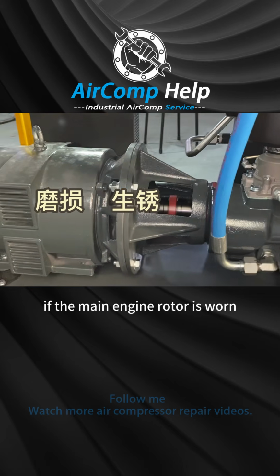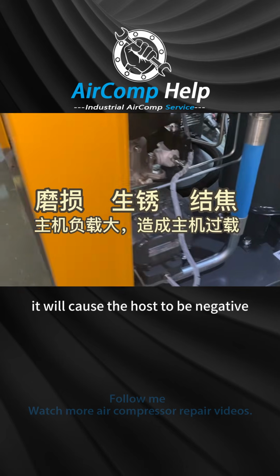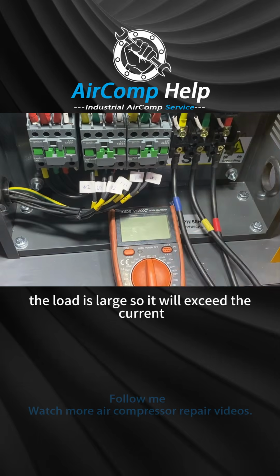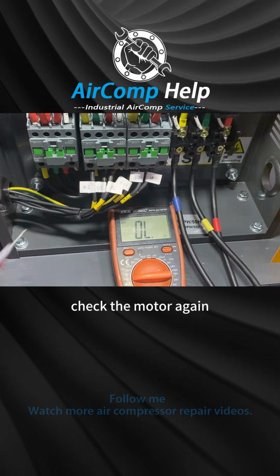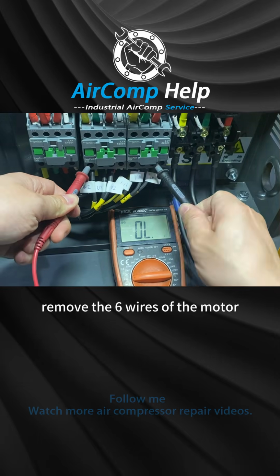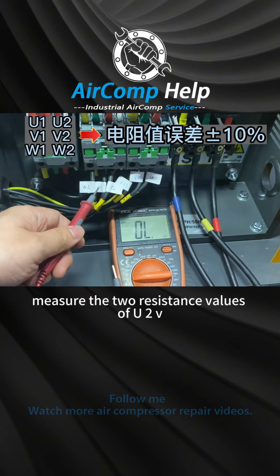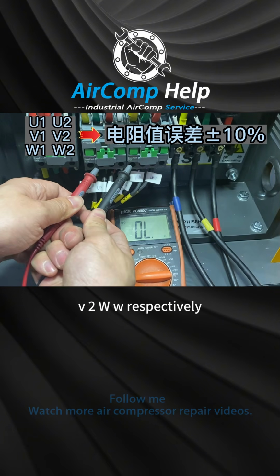If the main engine rotor is worn, rusted, or the oil is gelled, it will cause the host load to be large, so it will exceed the current. If there is no problem with the host, check the motor again. Remove the 6 wires of the motor. Measure the resistance values of U1U2, V1V2, W1W2 respectively.